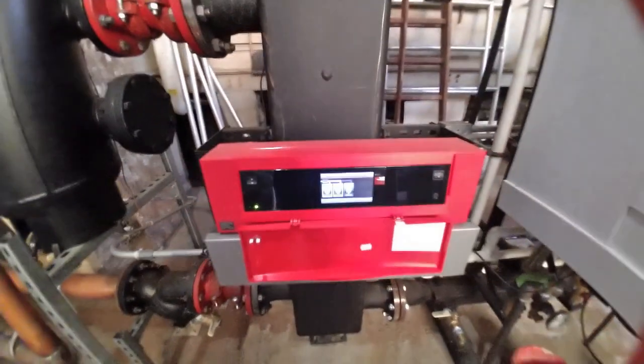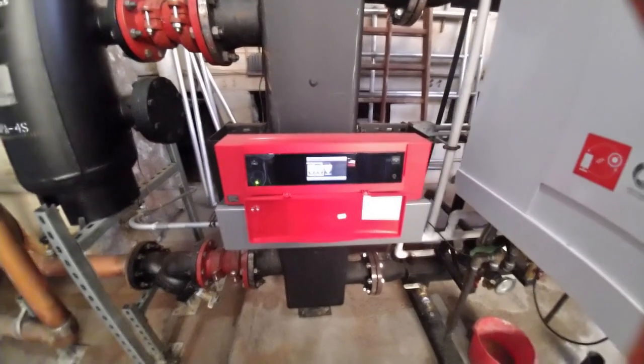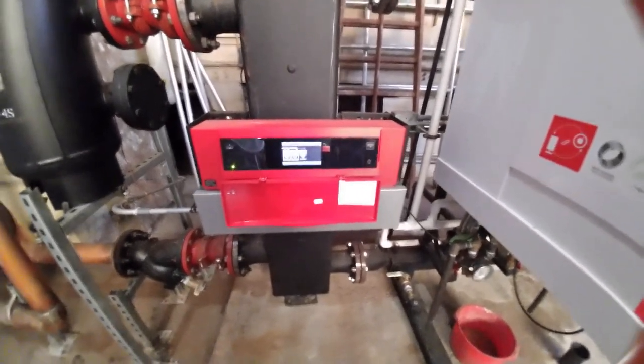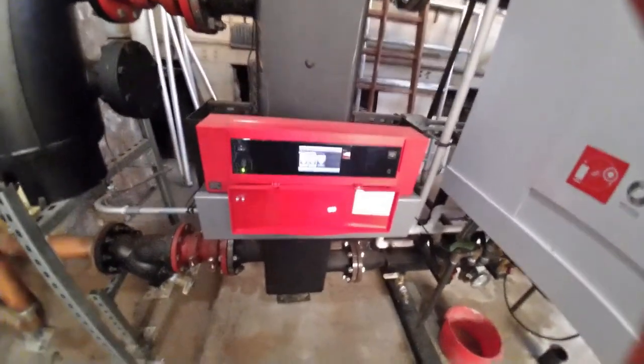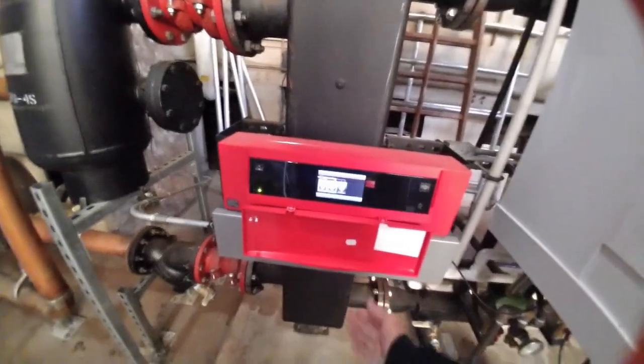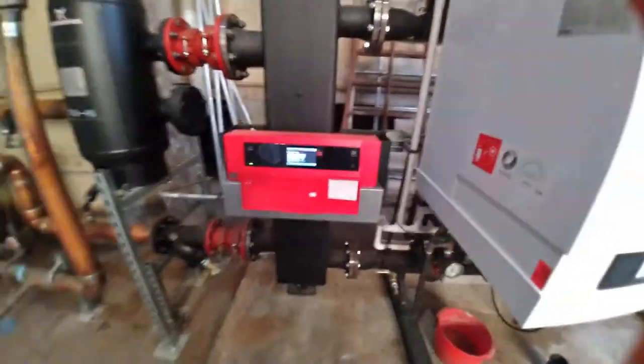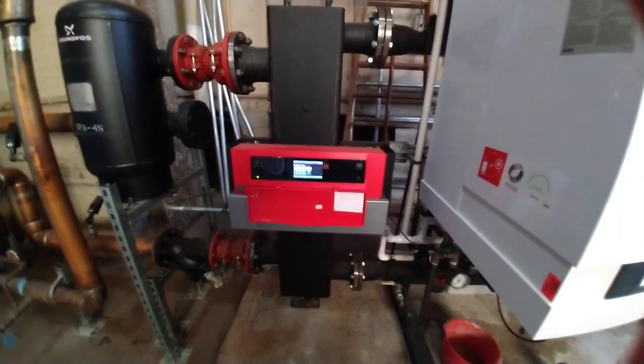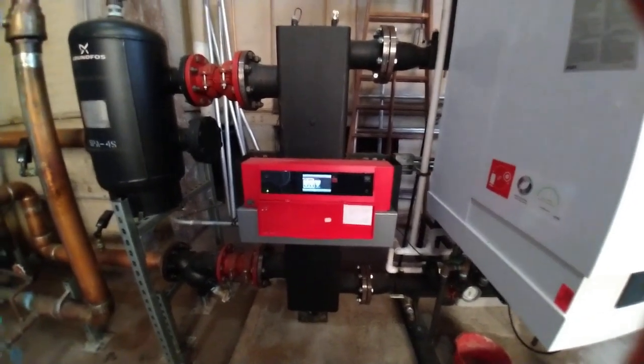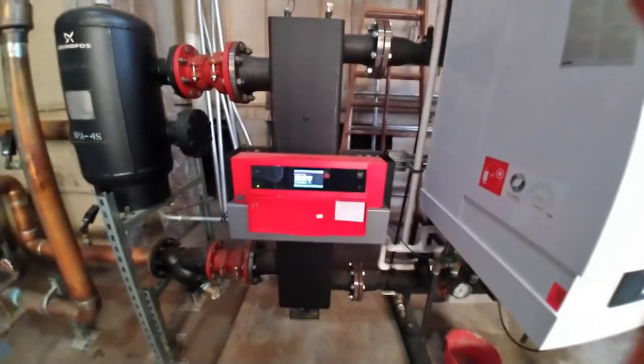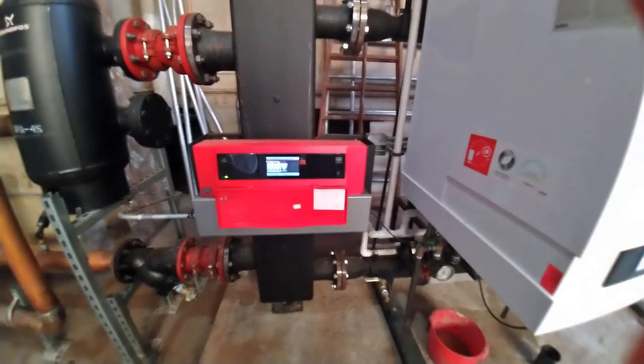This control is used to stage all the boiler operations, turn everything on and off, warm weather shutdown of the main system circulator, and give us all the high efficiency control we need to stage things properly to get maximum energy efficiency and cost savings out of these boilers.